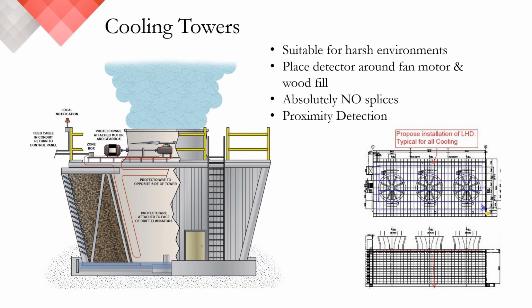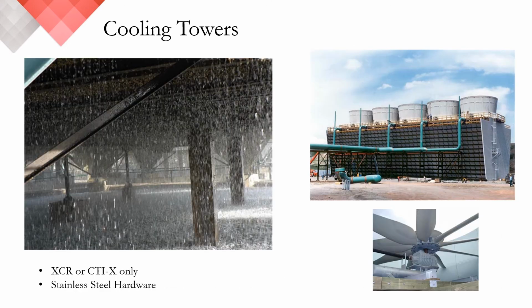In most cases, we see linear heat detection being used and applied in several areas, including around the fan motor, gearbox, and down into the structure itself. Again, the primary objective here is proximity detection to the primary equipment. Due to the environmental challenges in these areas, we recommend there be no splices anywhere in the application. And you can see from these images the environmental challenges these structures pose.